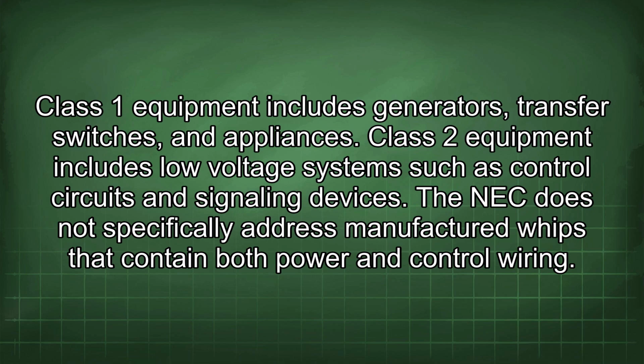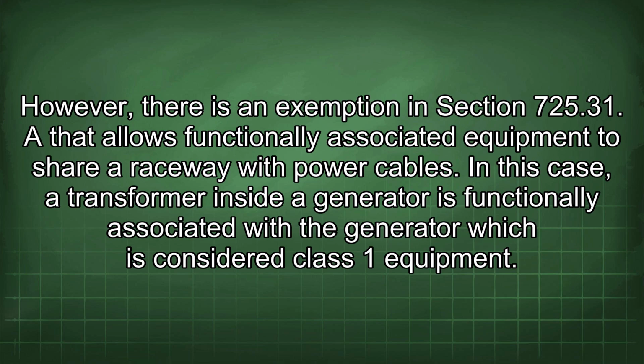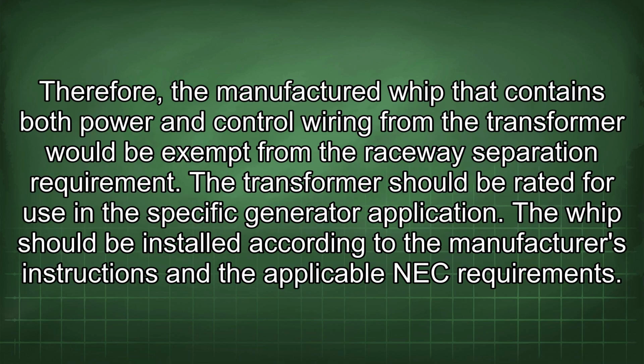The NEC does not specifically address manufactured whips that contain both power and control wiring. However, there is an exemption in Section 725.31 that allows functionally associated equipment to share a raceway with power cables. In this case, a transformer inside a generator is functionally associated with the generator, which is considered Class 1 equipment.